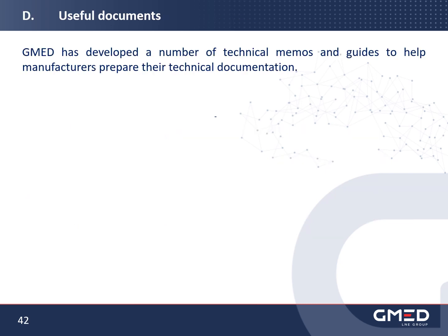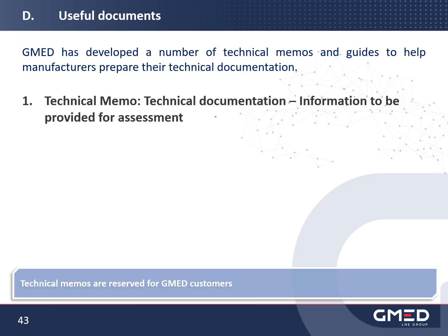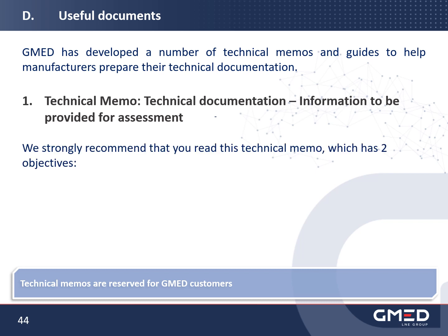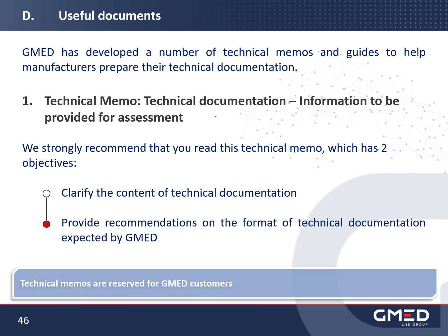To help manufacturers design and ensure the completeness of their technical documentation, GMED has developed several documents. In particular, you'll find the technical memo, technical documentation, information to be provided for assessment. We strongly advise you to take note of this technical memo when drafting your technical documentation or when submitting your formal application for certification. This technical memo has two objectives. Firstly, to clarify the content of technical documentation, and secondly, to provide recommendations on the documentation format expected by GMED.